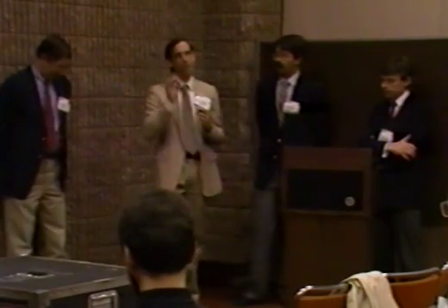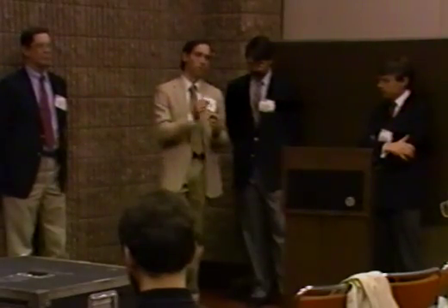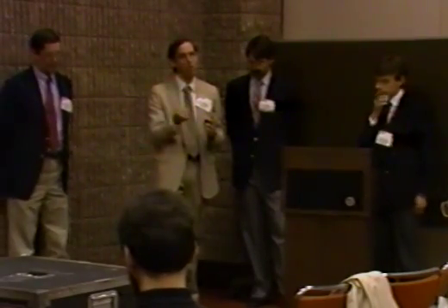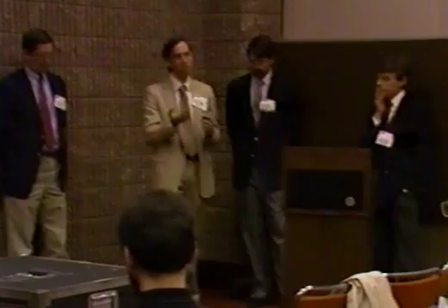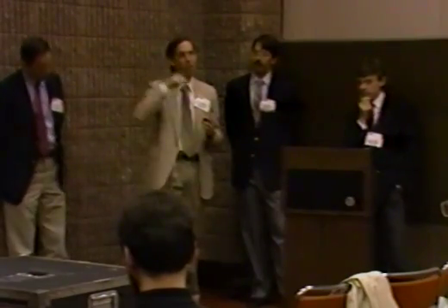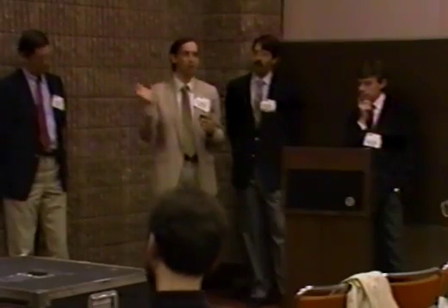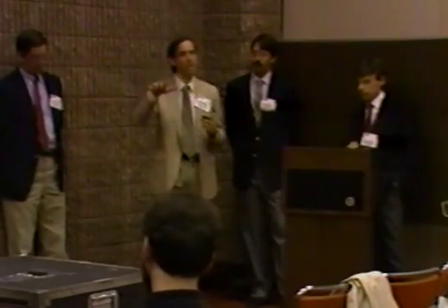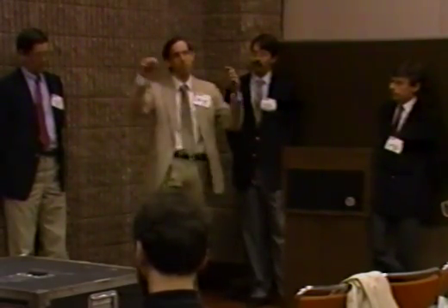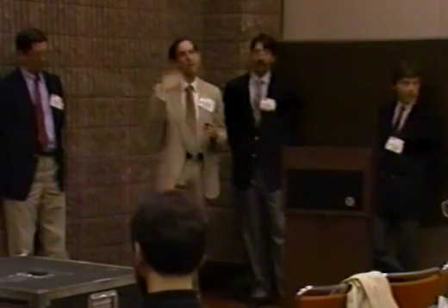The problem with doing it in this situation, and I think it's the same problem that I questioned Dr. Nielsen about his scanner, is that if you put light in at a point and collect it from the same point, you can get a specular reflection, and you also weight very short paths of light that happen to be momentarily backscattered, a rather rare event, back into the volume. You get a very large heterogeneity in path lengths and sample volumes. So it's a much more imprecise measurement than using two small fibers separated by a fixed distance. It really has to do with the sampling.